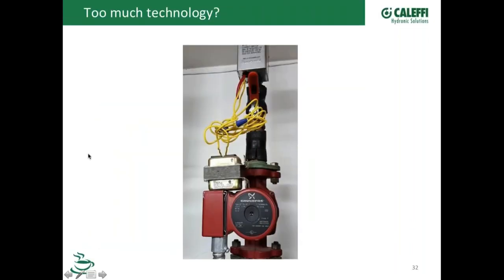All right. Now, I'm not exactly sure what's going on here, but probably a little bit of over-engineering. Rarely should you need to have a pump and a zone valve right against it like that. Most of the new pumps now have check valves that are built into them or that you can slip right into the volute here. So if that pump isn't running and a pump next to it, for example, is, you shouldn't be getting any ghost flow going through that. But that's kind of a clever application.